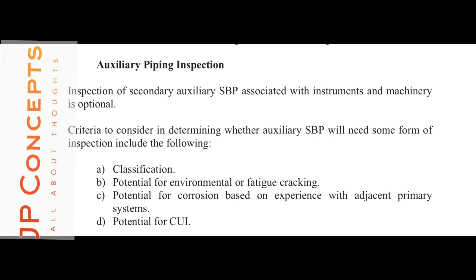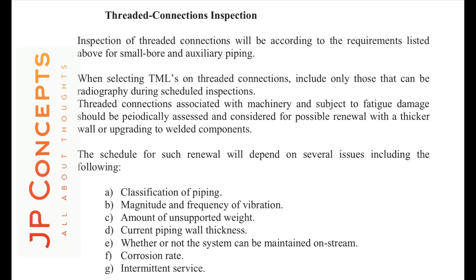Threaded connection inspections are also similar to the small bore and auxiliary piping inspection requirements. When selecting TMLs or CMLs on threaded connections, include only those that can be radiographed during scheduled inspection. Radiography only possible. Threaded connections associated with machinery and subject to fatigue damage should be periodically assessed and considered for possible renewal with thicker wall or upgrading to welded components. The schedule for such renewal will depend on classification of piping, magnitude and frequency of vibration, amount of unsupported weight, current piping wall thickness, whether or not the system can be maintained on stream, corrosion rate, and intermittent service.